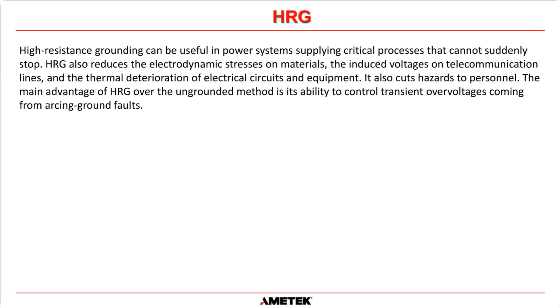Now we're going to discuss high resistance ground systems. High resistance grounding can be used in power systems supplying critical processes that cannot suddenly stop. So pretty much any petrochemical refinery or chemical plant that requires continuous operation, and stopping that process would cause danger to people, then you don't want something that's going to cause that system to suddenly stop because of a fault somewhere else. So that's why most refineries and petrochemical plants use a high resistance ground system. It also cuts hazard to personnel.